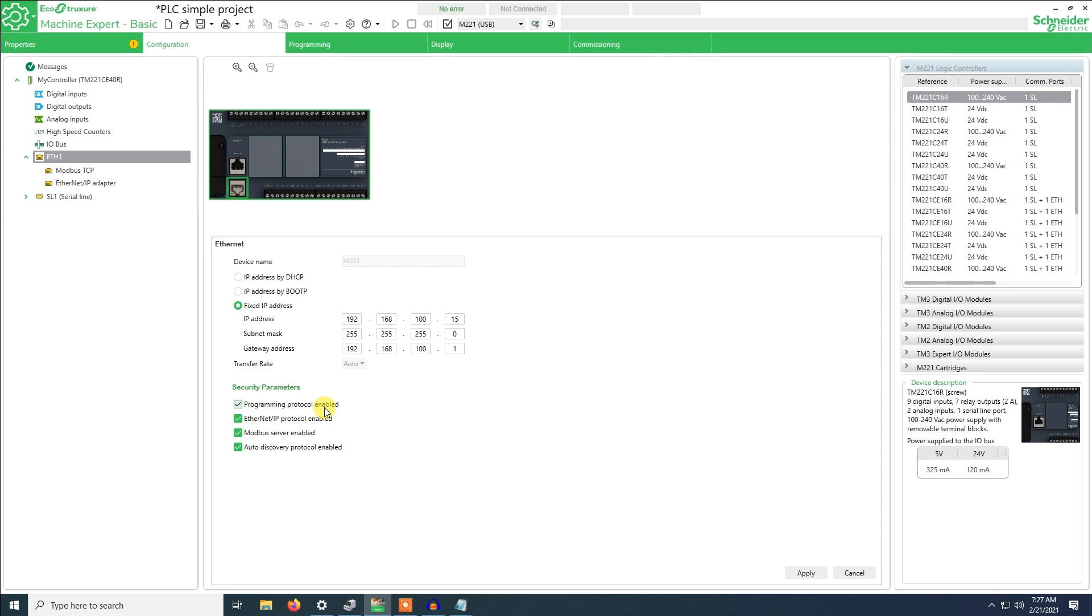The Modbus server is when we will use a PLC as a slave for an HMI, so that we can share information like runtime, the input signal status like a float switch or for a breaker. Auto discovery is when we use Schneider software that we can discover this PLC automatically.